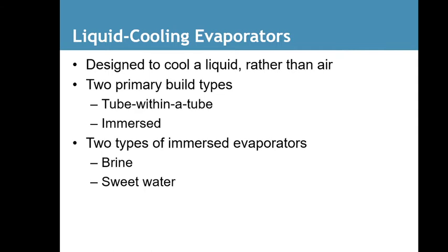Liquid cooling evaporators are designed to cool a liquid rather than air. Two primary build types are tube within a tube and immersed. Two types of immersed evaporators are brine and sweet water.